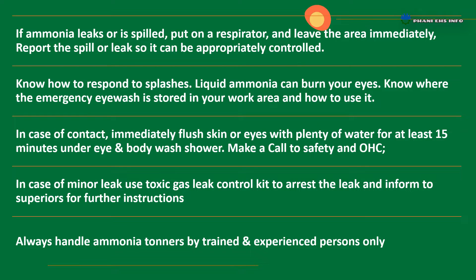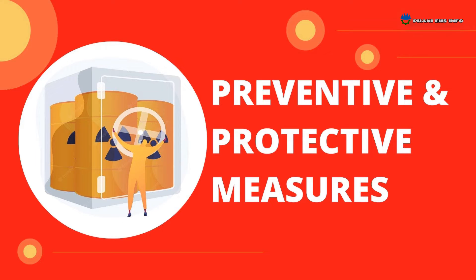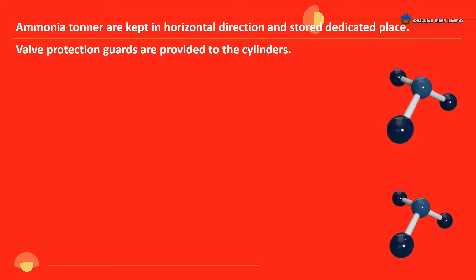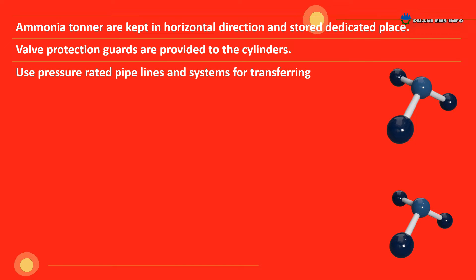Always handle ammonia tonners by trained and experienced persons only. Preventive and protective measures at ammonia storage and handling areas — Engineering Controls: Ammonia tonners are kept in a horizontal direction and stored in a dedicated place without causing any harm or damage to the spindle valve of the cylinder. Valve protection guards are available for the cylinders. Use pressure-rated pipelines and systems for transferring.